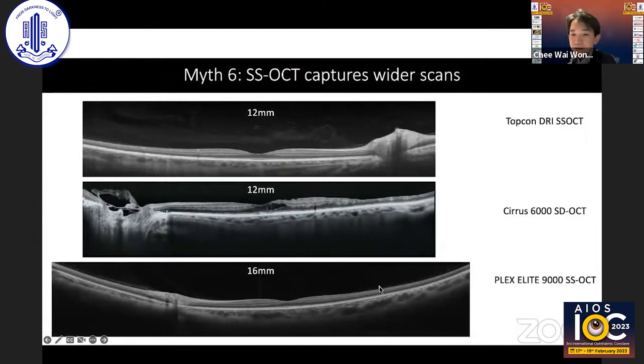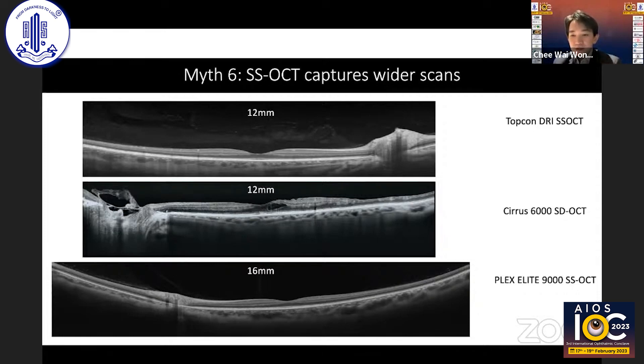Myth number six: swept source OCT can capture wider scans than spectral domain. The technical differences between the two are not limiting factors for scan width, so both instruments are capable of capturing wide scans. Commercially available OCTs can now scan up to 12 millimeters, which has become the standard, while the Plex Elite swept source OCT can capture up to 16 millimeters.